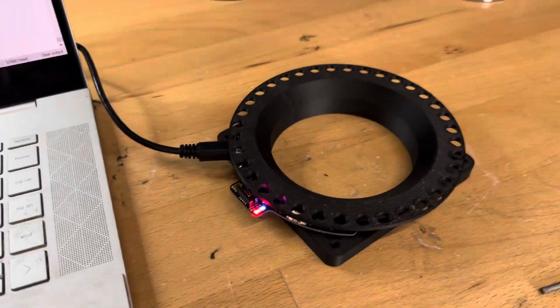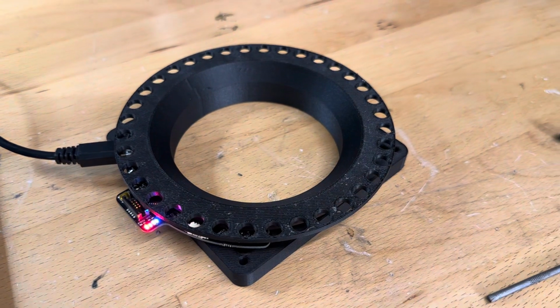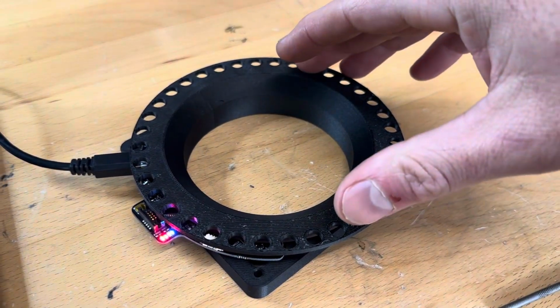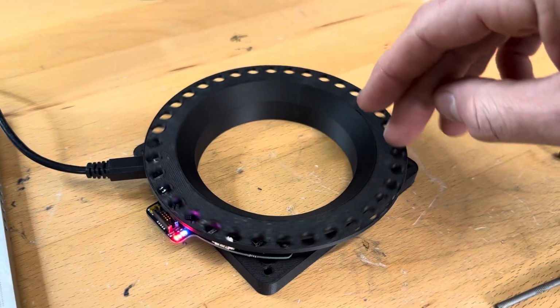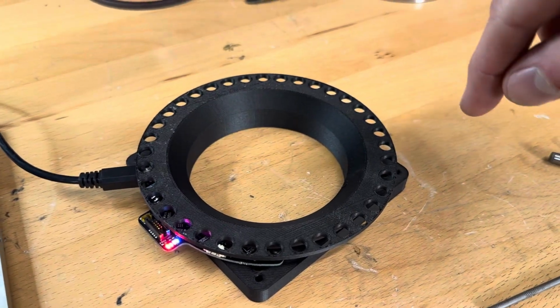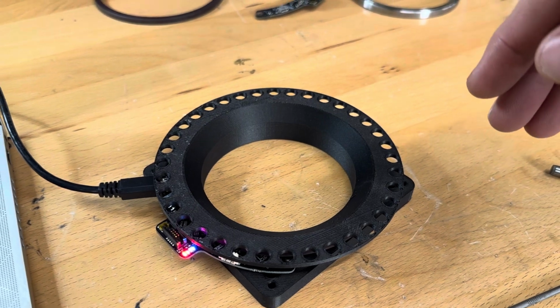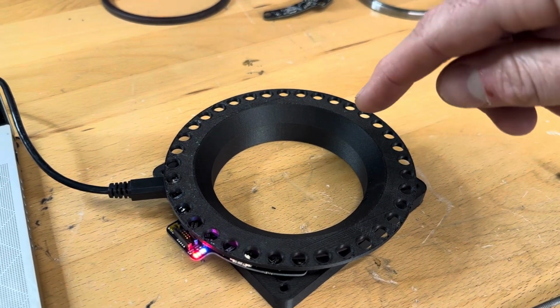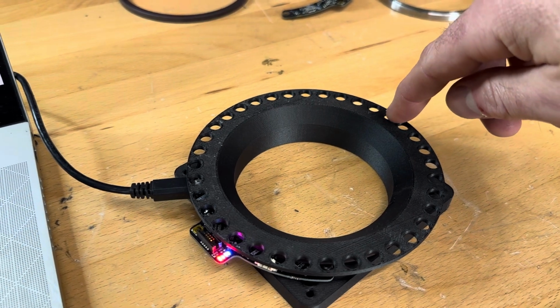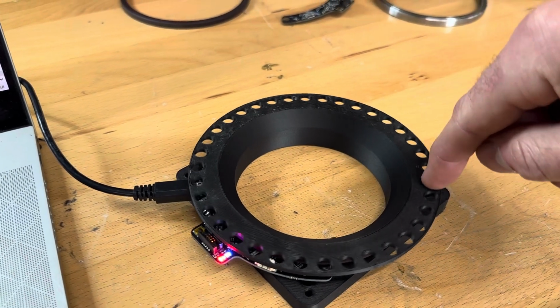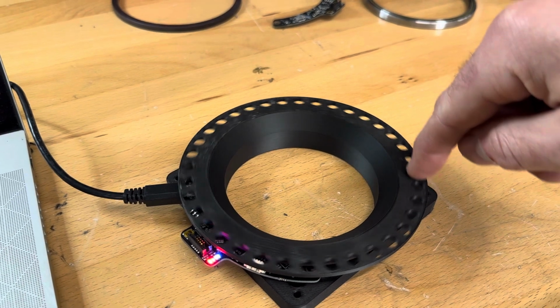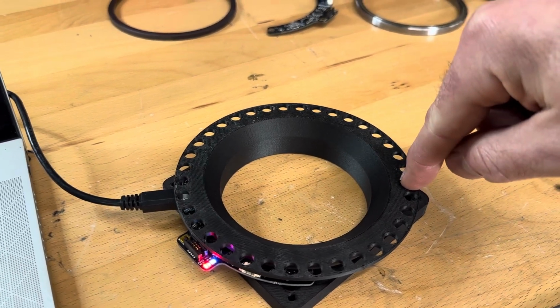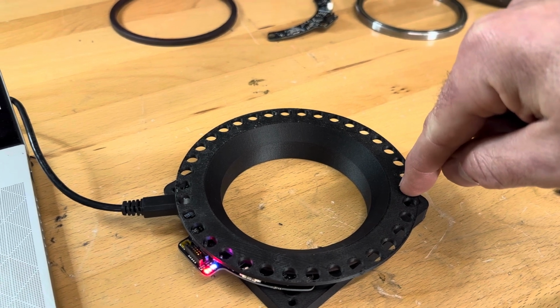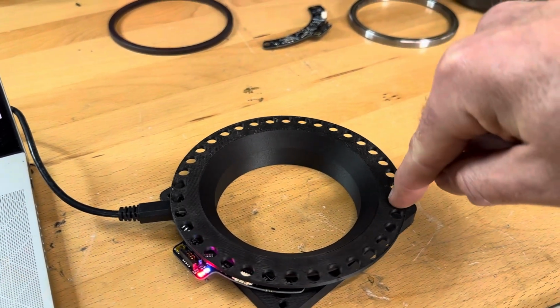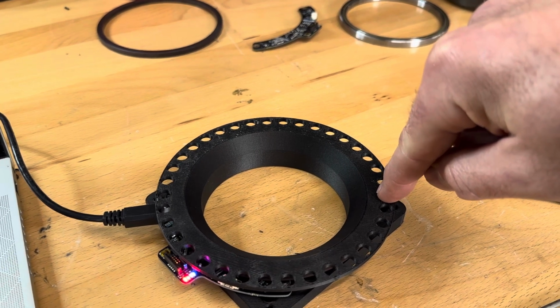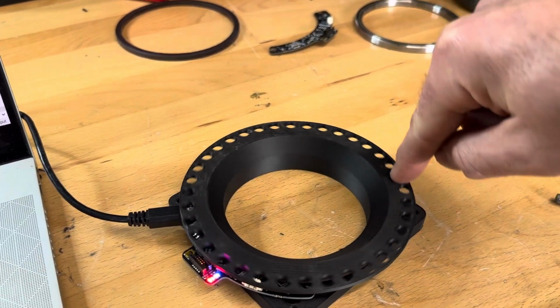So briefly gonna attempt to explain this, and it can be hard to do without some graphics, but this sensor is absolute. It will say 0 to 360 degrees with respect to itself. That 0 and 360 degrees is always going to be repeatable, but it may not actually match true measured degrees. So say this is my 0 point back here, and I want to go to 45 degrees. If you don't do an advanced calibration, whatever number happens here will always happen there. Let's say for this example, it's 43 degrees. But if you really want that to tell your robot that that's actually 45 degrees and you've calibrated it, then the sensor gives you a method to do that.